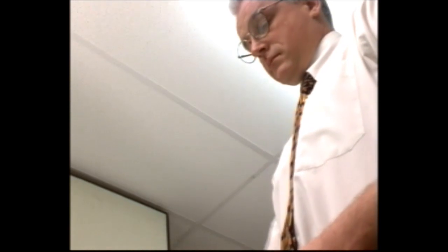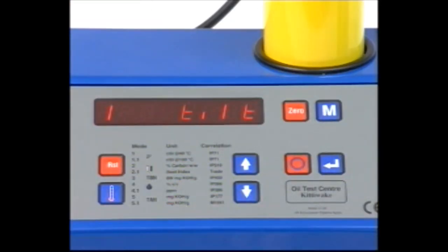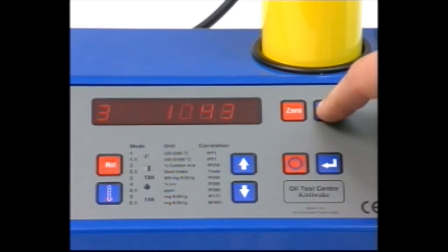To determine the reference value, place the cell onto the console and remove the end cap. Select mode 3 on the unit.